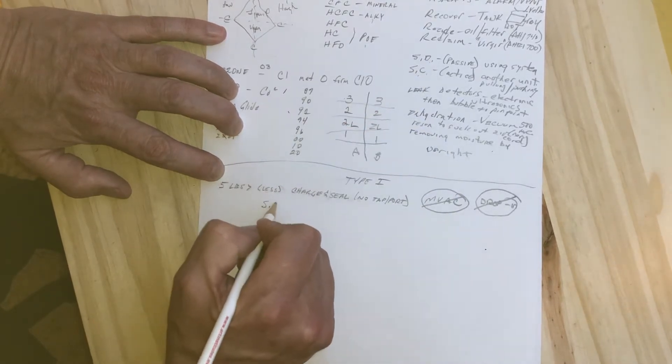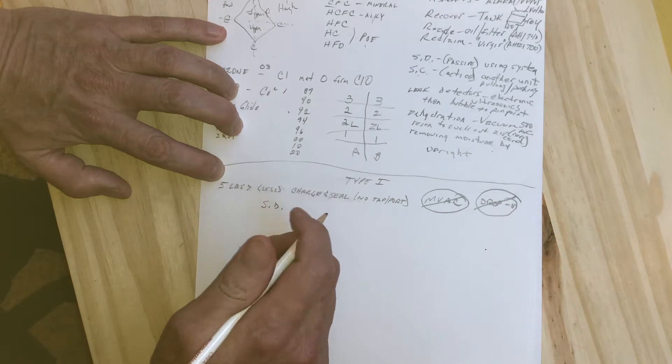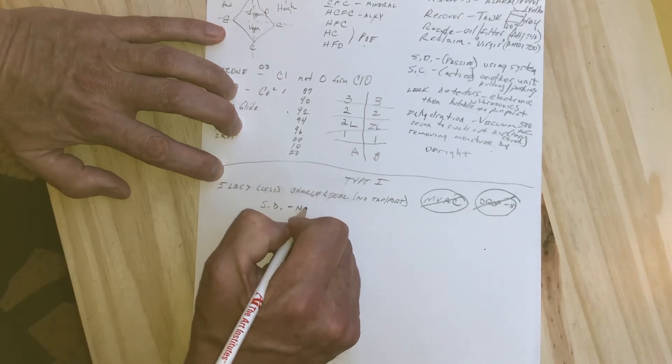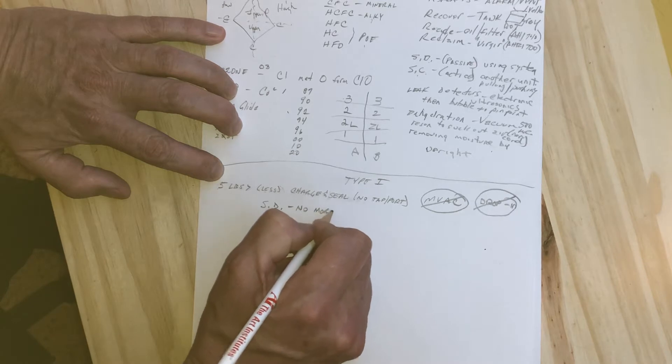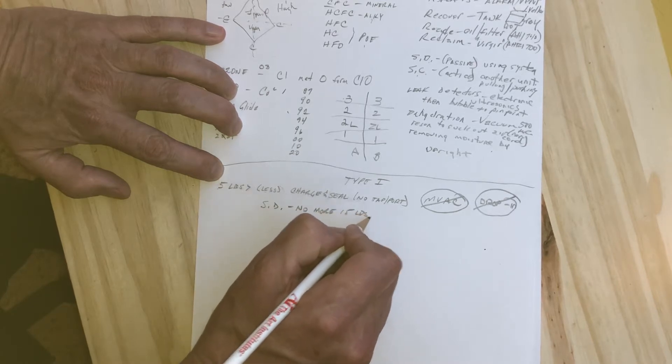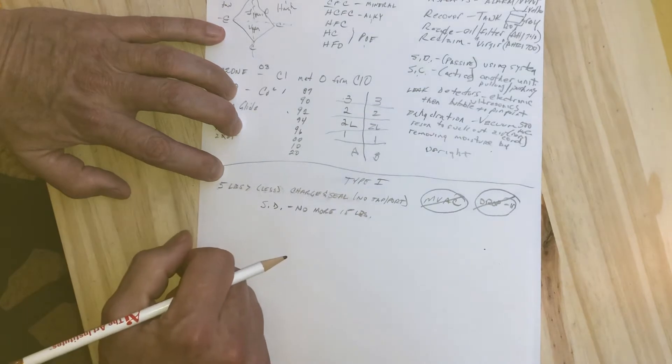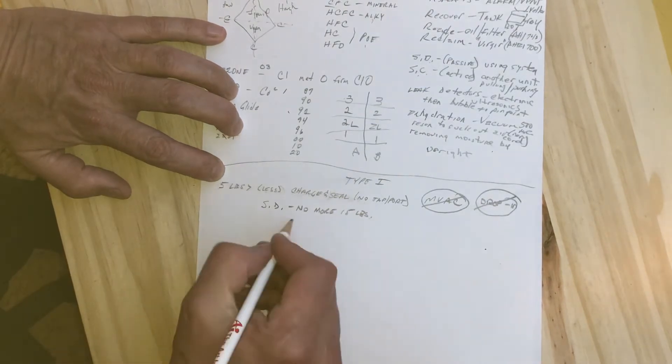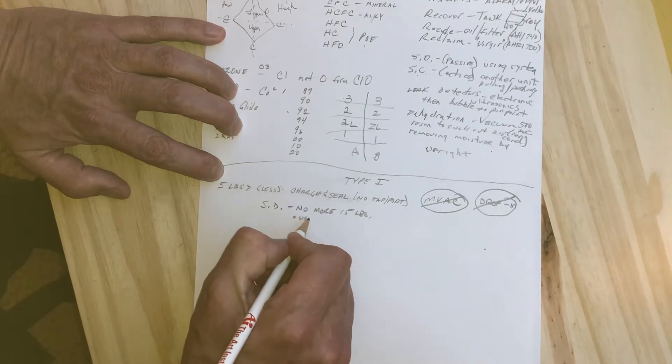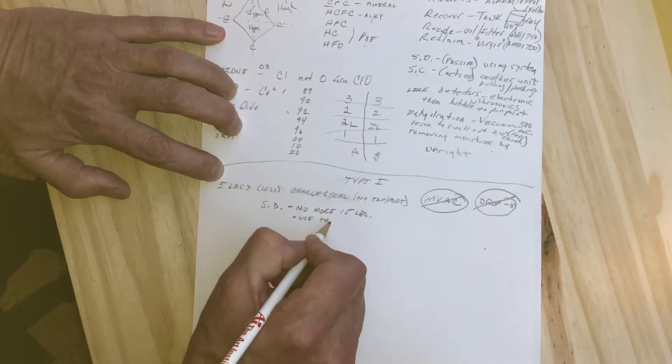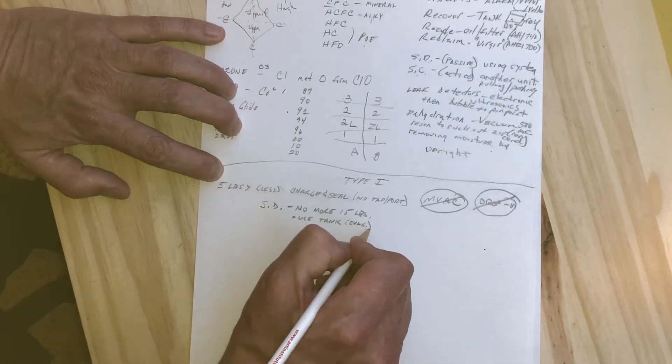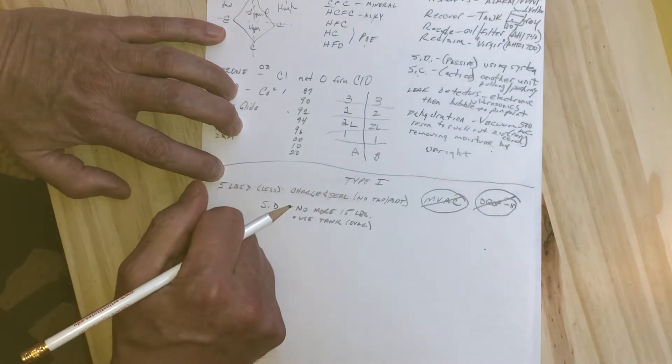Let's talk about the system-dependent recovery process for Type 1 appliances. No more than 15 pounds if you're doing system-dependent. It can be done in a non-pressurized container, in a bag, or an evacuated recovery tank, which can act as a system-dependent recovery device.